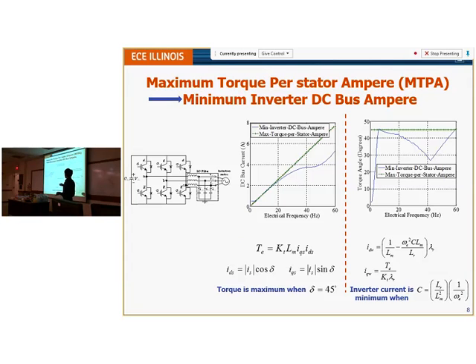Now, in other words, we have this filter. Let us not look at the filter just as a harmonic mitigator, because generally in most of the drives we look at filters as components to remove or eliminate harmonic components. But this can also be seen as a provider of the magnetization current for the induction motor.